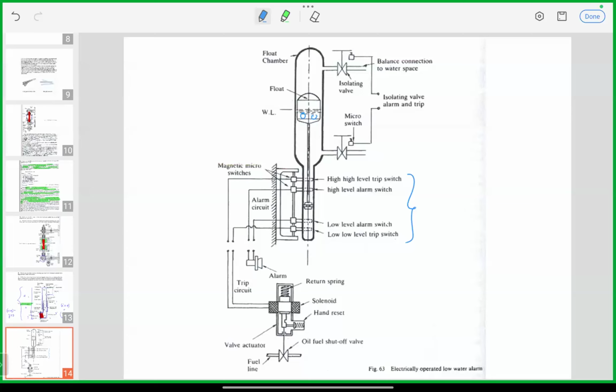control system, level control system, and that is why in most modern boilers you will find DP transmitters fitted. These DP transmitters are able to detect the level, and they will be able to generate the alarms. They can be used to trigger the safety system, that means safety and shutdown system. So multiple uses can be taken with the help of the DP transmitter, and the possibility of damage to this float is also eliminated.